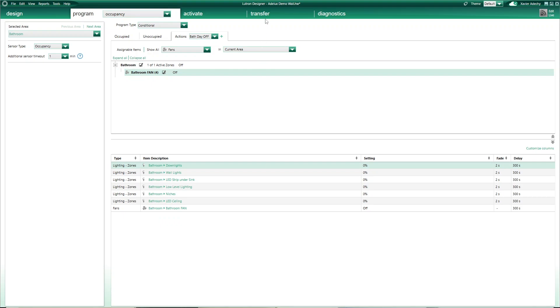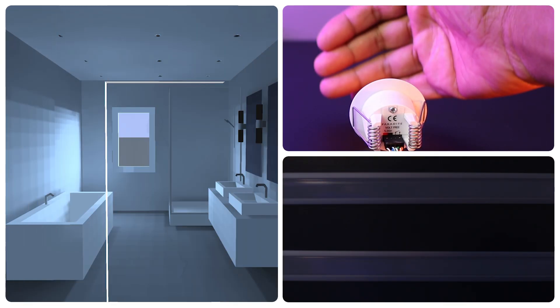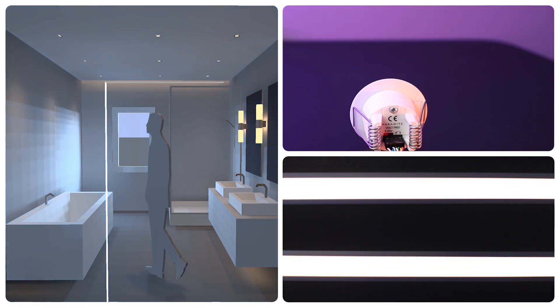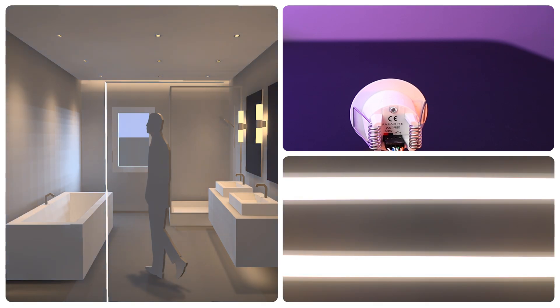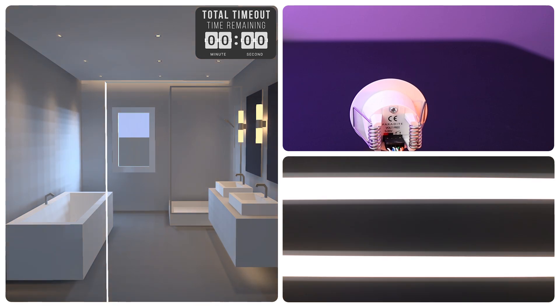Let's upload the program and test it. During daytime, when I walk in the bathroom, my Bath Day On action is activated — lights are very bright. And when I exit the bathroom, the sensor timeout kicks in, and if during that 6-minute period no motion is detected in the room, the Lutron system will execute the programming in the Unoccupied tab and turn the lights off.